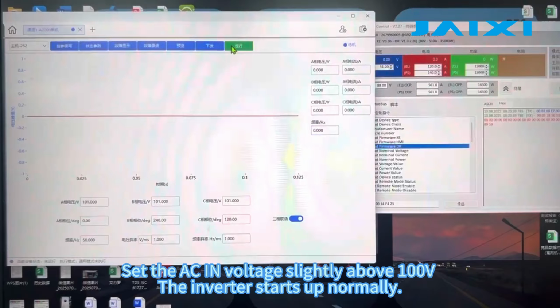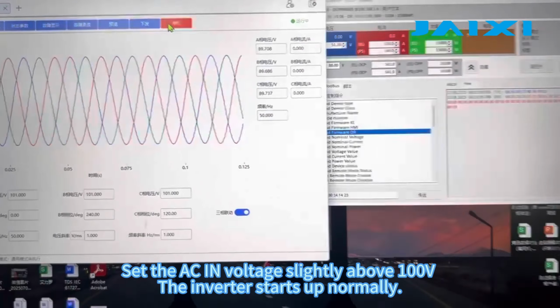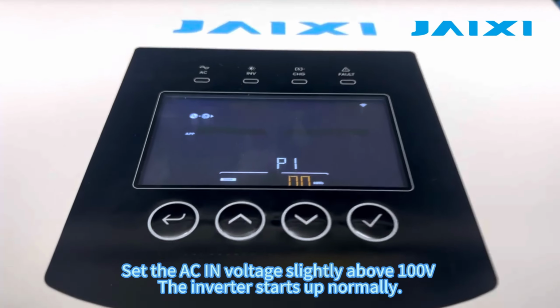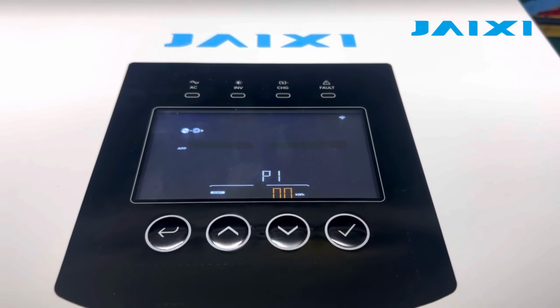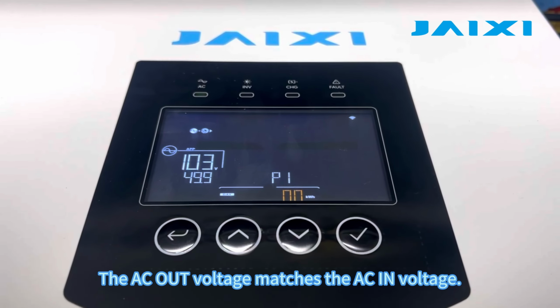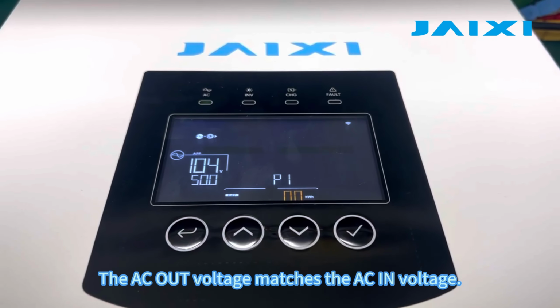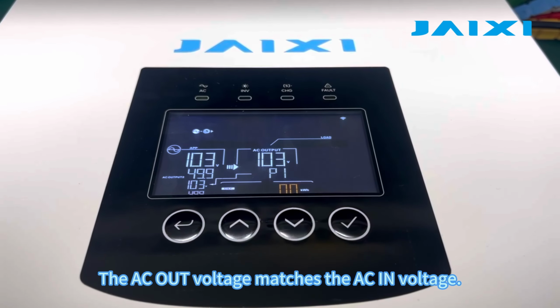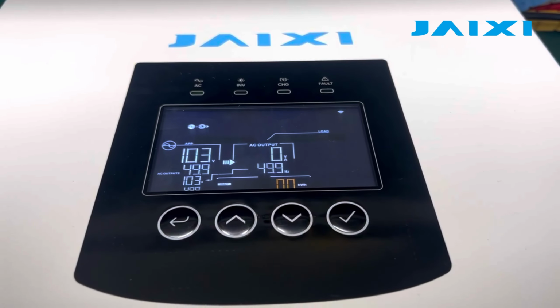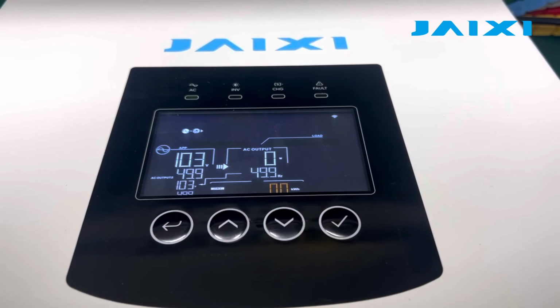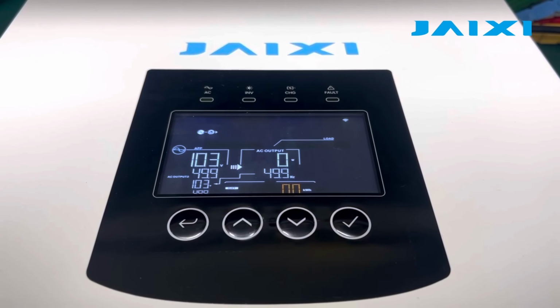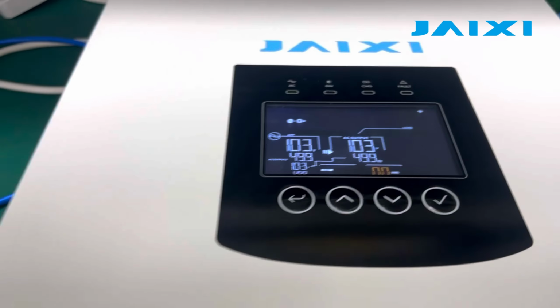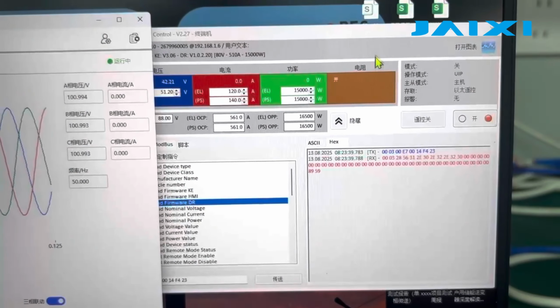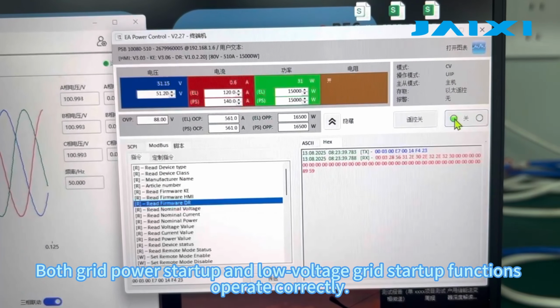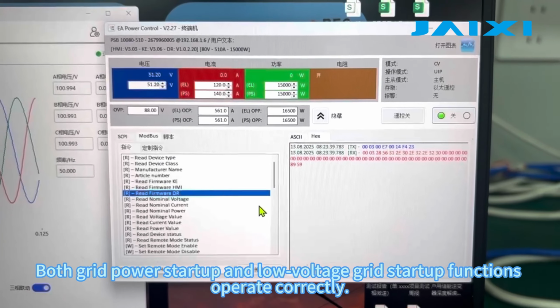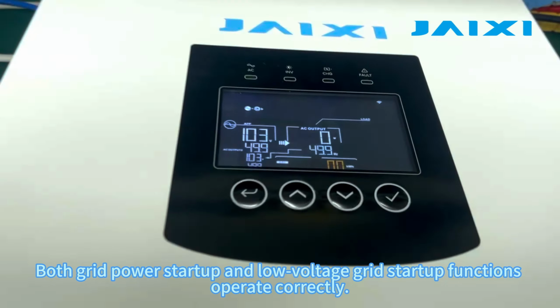Set the AC in voltage slightly above 100 volts. The inverter starts up normally. The AC out voltage matches the AC in voltage. Both grid power startup and low voltage grid startup functions operate correctly.